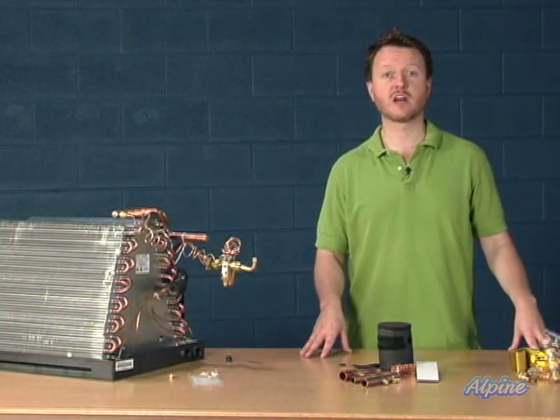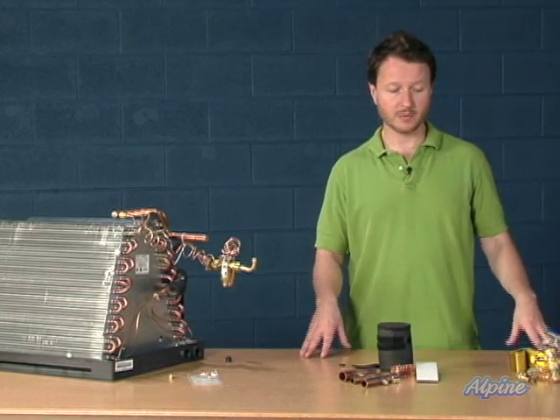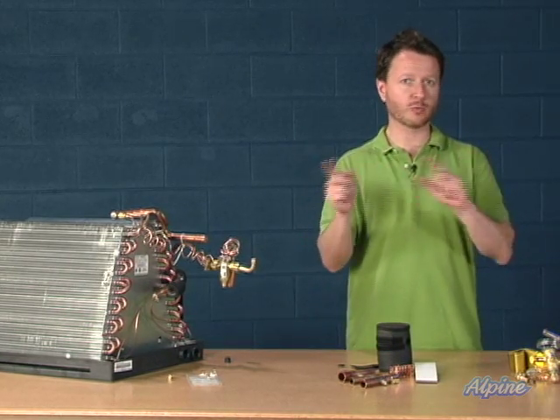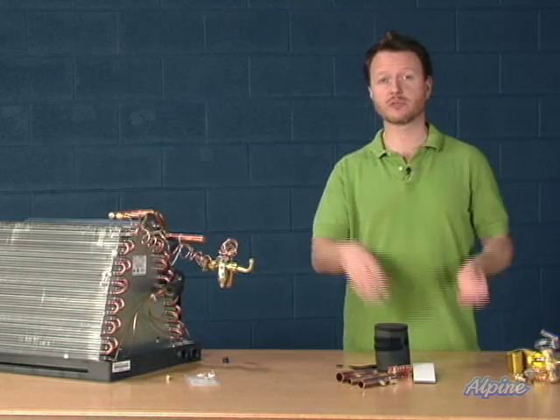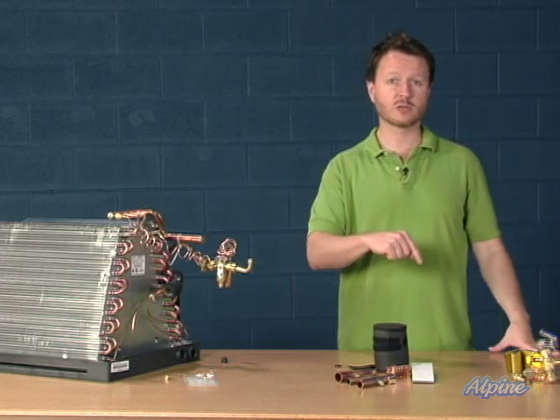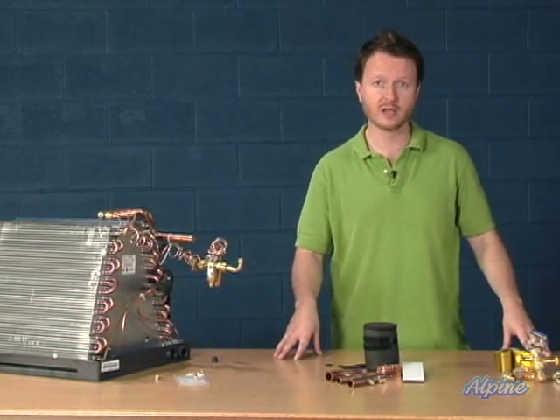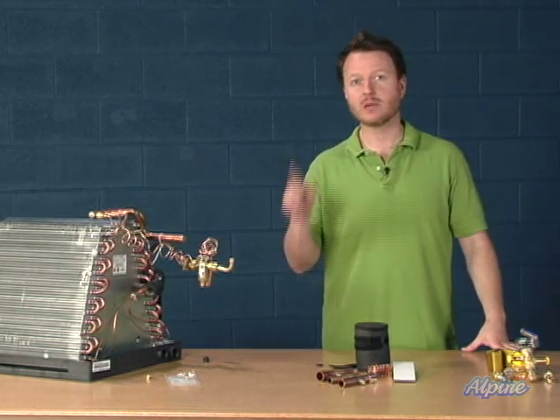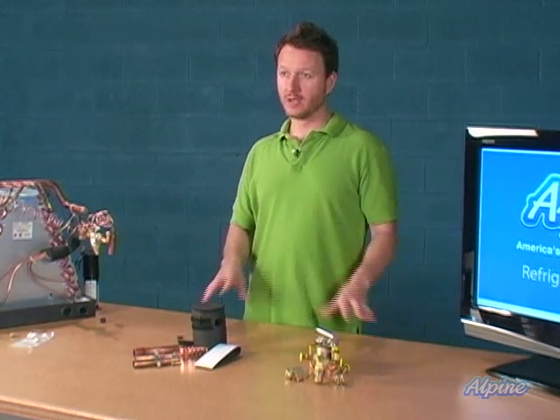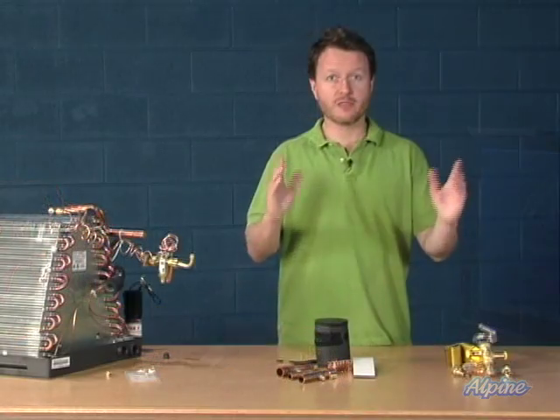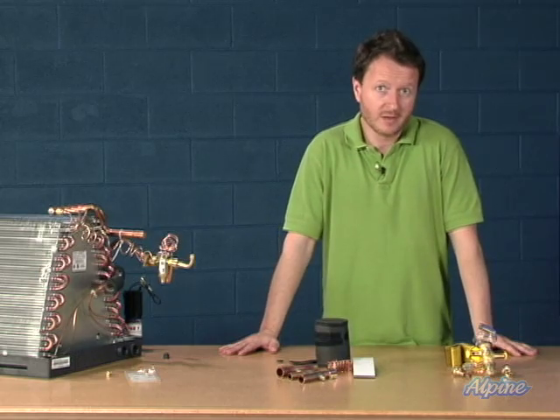Thermostatic expansion valves come in types that work with different refrigerants. So we have R22, that's one refrigerant type. We have R410A. Make sure you get the one that works with the refrigerant type that you're using for your equipment, and make sure that it covers the tonnage range of the outdoor equipment, that outdoor condenser or heat pump. Those are some key points you'll want to note about refrigerant regulators.